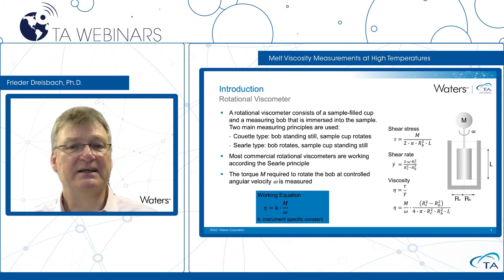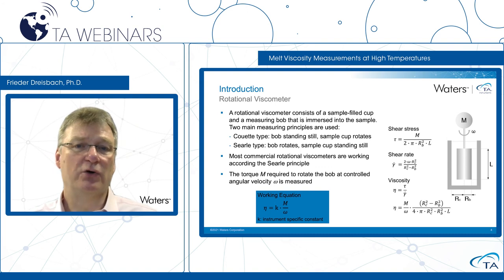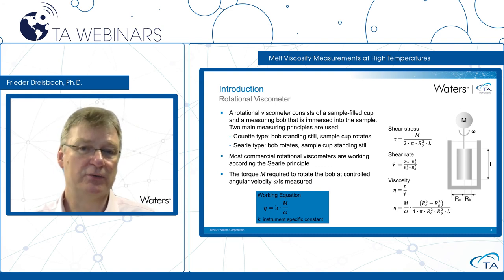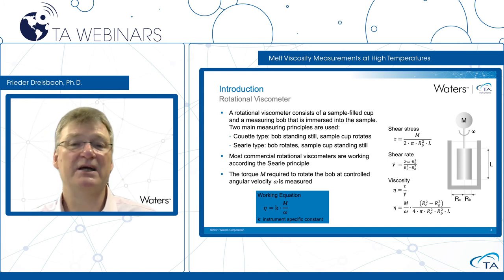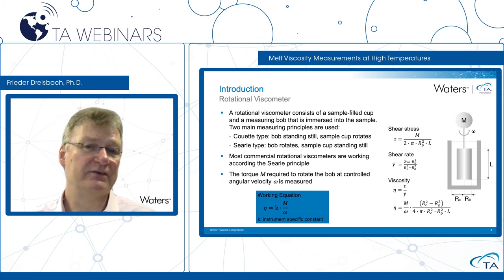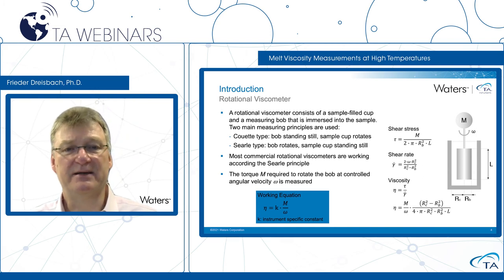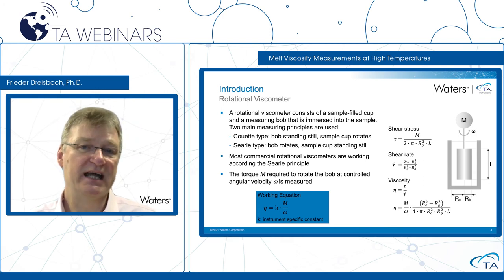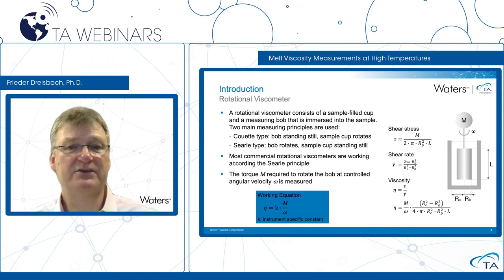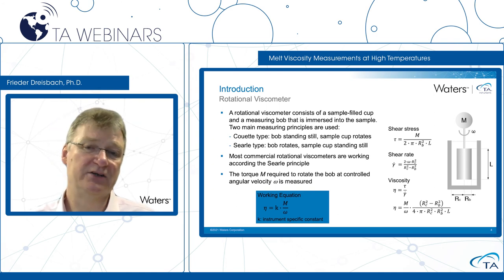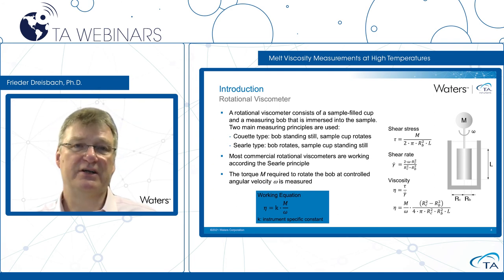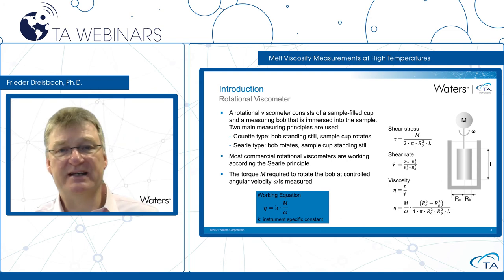Practically, the instrument-specific constant K is determined by a measurement with a reference fluid of known viscosity. If we know the viscosity (the left side of our equation), measure the torque M, and control the angular velocity omega, we have all quantities except K. So with a reference measurement using a reference fluid, we can determine K and use this later for measurements with unknown fluids.